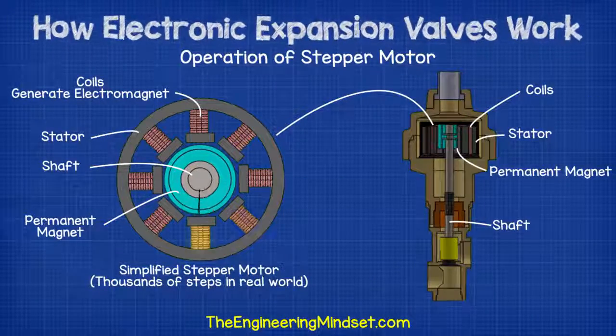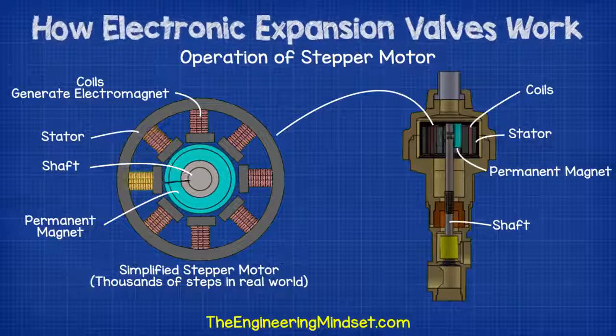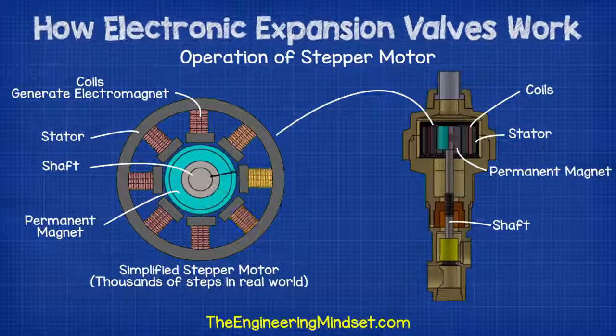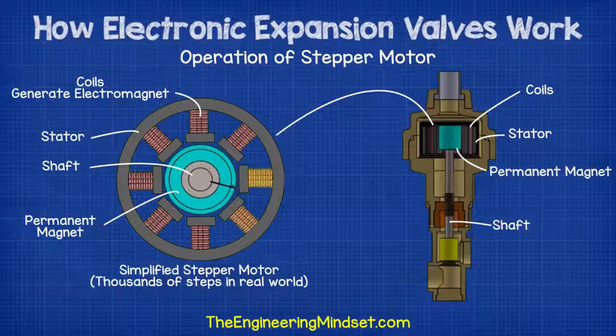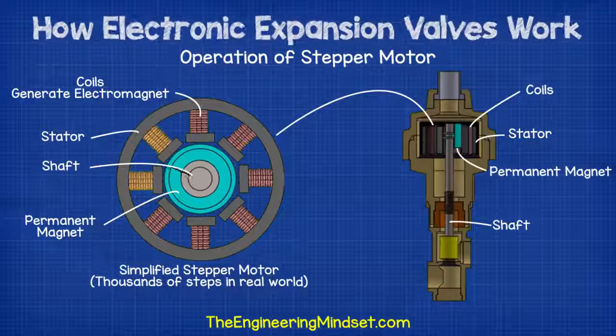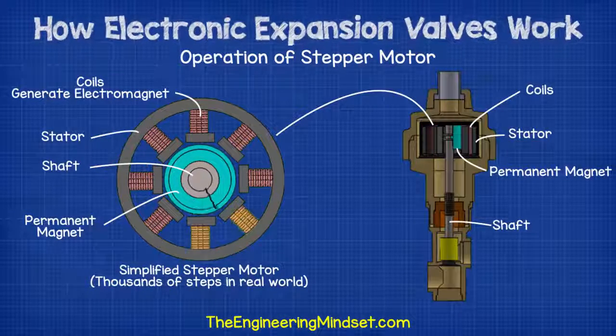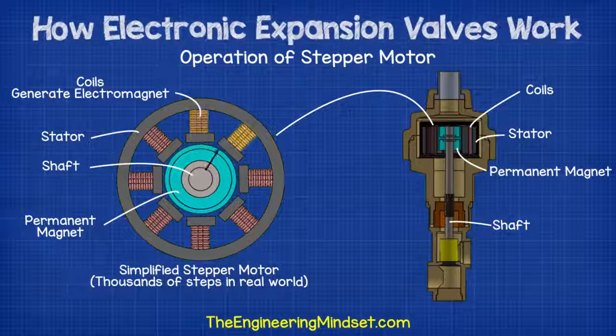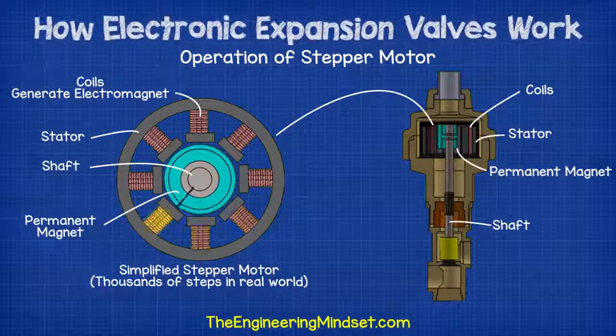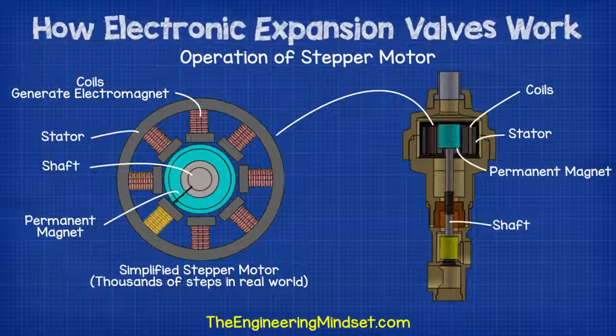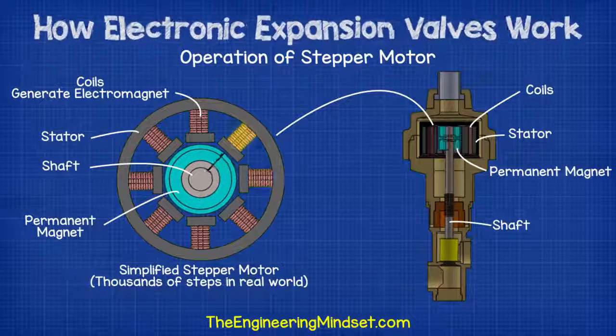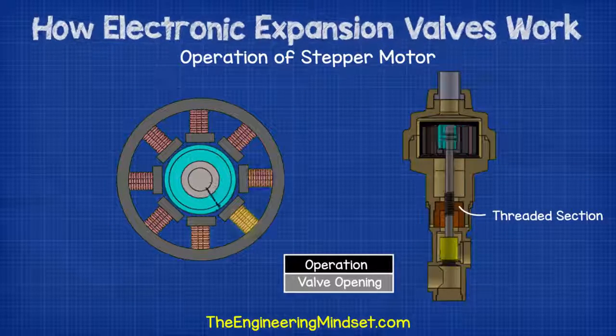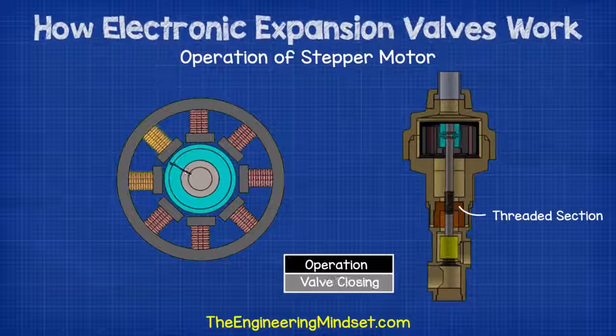the coils and create an electromagnetic field and vary its polarity. This forces the permanent magnet to rotate clockwise or counterclockwise depending on the polarity generated. Each time a signal is sent, the permanent magnet will rotate a fraction of a revolution to provide very accurate adjustments to the superheat. The shaft, which is connected to the permanent magnet, will also rotate, and as it does so, the threaded section inside the holder will cause the assembly to be pulled down.